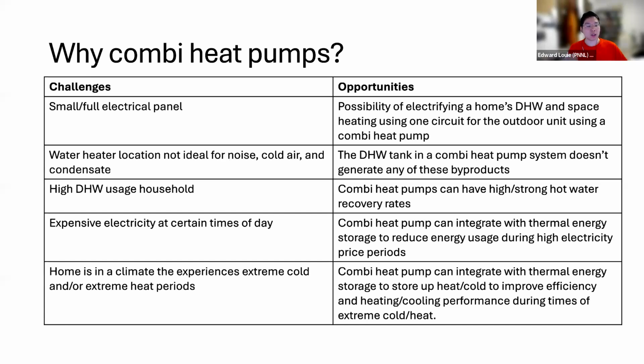And so you get really good reheat rates. And then systems that have thermal energy storage integrated with the system can produce heating or cooling without running the compressor at a high level, or even running the compressor at all.